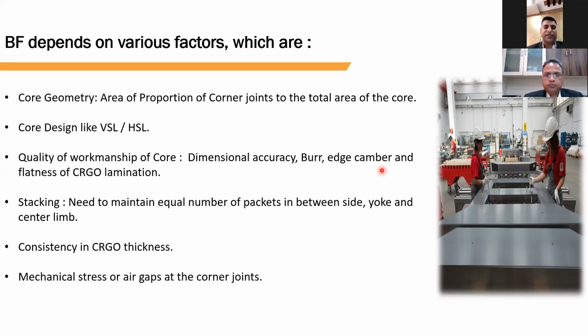The last one is flatness of the CRGO lamination. Sometimes the property of the CRGO coil itself is such that after cutting the slit coil, the lamination is not flat—this is called bow shape. This impacts no-load losses because it creates an air gap during stacking at the core assembly stage. These are the points where workmanship plays a major role in building factor measurement.